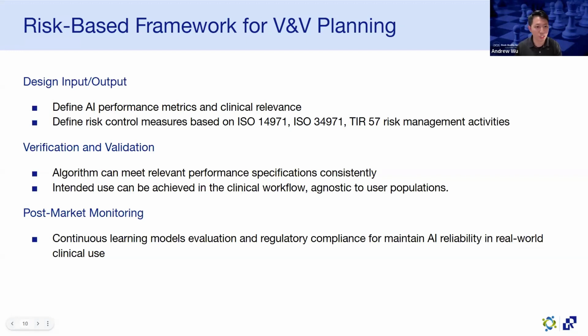And lastly, post-market monitoring is critical. Like I said just now, the model will degrade over time because of the distribution differences of the inference data. So it is absolutely critical to keep collecting information after device deployment. And this information will help the sponsor to characterize the uncertainty of the device output, and obviously use a predetermined change control plan as a measure to configure and calibrate the device regularly. Okay. All right, next slide, please.